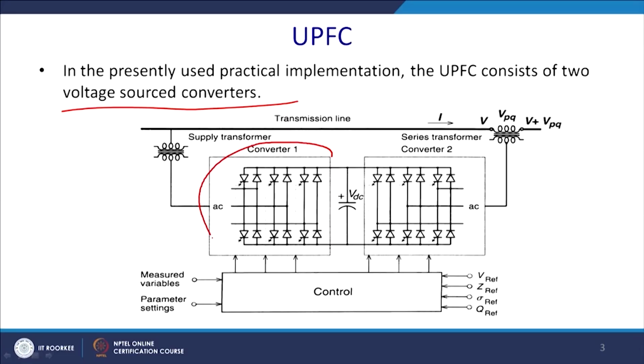So, this was basically the series part, and this is the supply transformer. It will inject the voltage in series with the supply, depending on the different phase angle, and this is basically the shunt part of it. Since it is connected in the transmission network, the rating of the switches is quite low; we require a coupling transformer to step down the voltage level. And you have measured variables, that is the voltage, power, V, P, Q and delta. So, we have to have a parameter setting for all, and accordingly the control setting will be there.